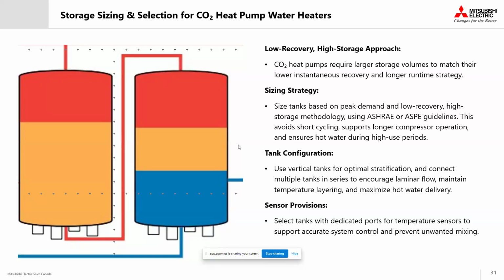So as Rizwan mentioned earlier, many CO2 heat pump water heaters follow a low recovery, high storage approach. Because these heat pumps don't recover as quickly as a conventional boiler, large storage volumes are needed to meet peak demand and support continuous decarbonized operation. As Rizwan mentioned, we're always looking to follow our ASHRAE or ASPE guidelines to size these tanks, so you avoid short cycling, prolonging compressor life and boosting system reliability.